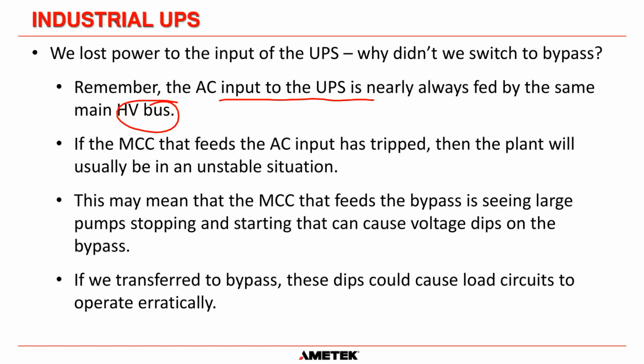So you've got to remember, the AC input to the UPS is nearly always fed by the same main HV bus back in an MCC somewhere, okay? If the MCC that feeds the AC input has tripped, then the plant will usually be in an unstable situation. So if you've lost a whole MCC, something bad has gone on, and the plant is going to start tripping things and putting them in a safe mode of operation.